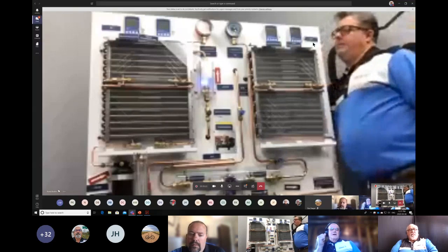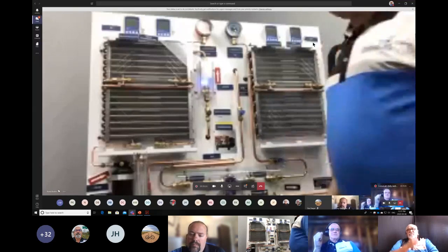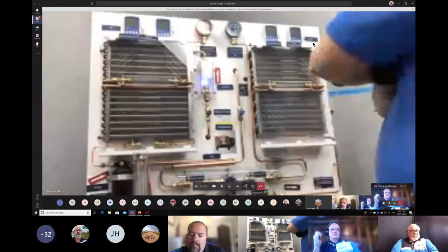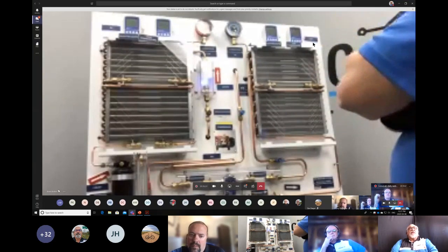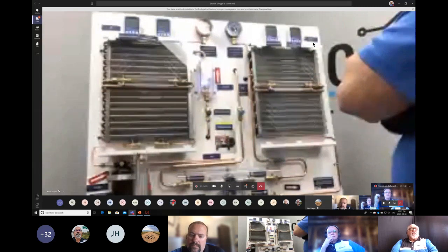And I just want to point out that when you make these measurements, both pressure and temperature, they should be as close to instantaneous as possible because they're changing. So don't read the pressure and 10 minutes later read the temperature. Try to do them both at the same time. Yeah. So remember to turn the bypass switch on there, Kevin.